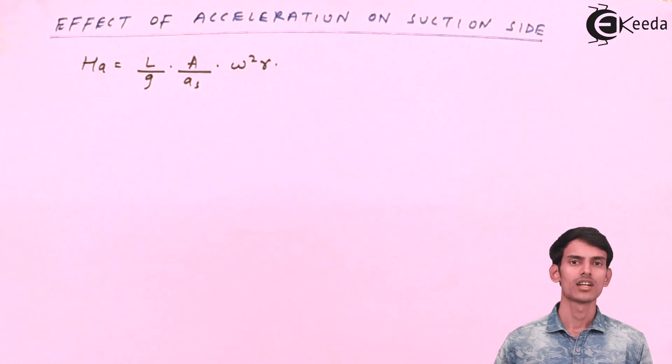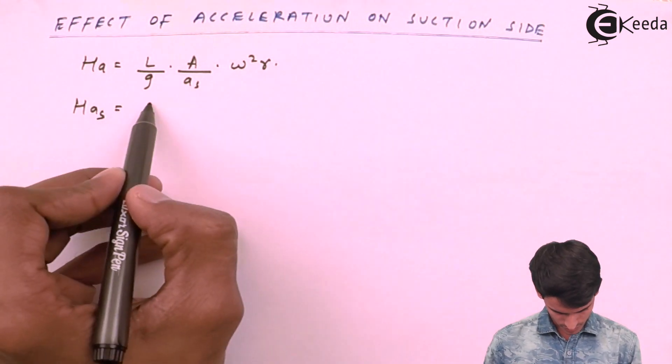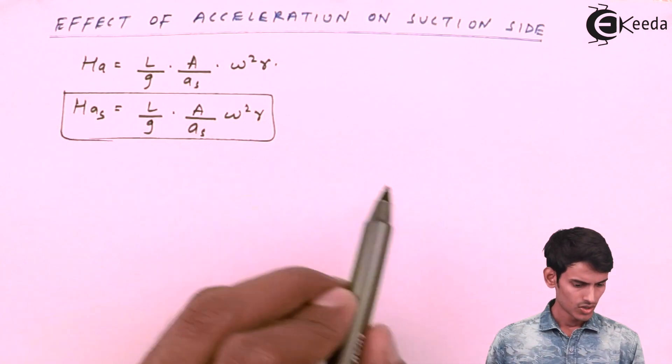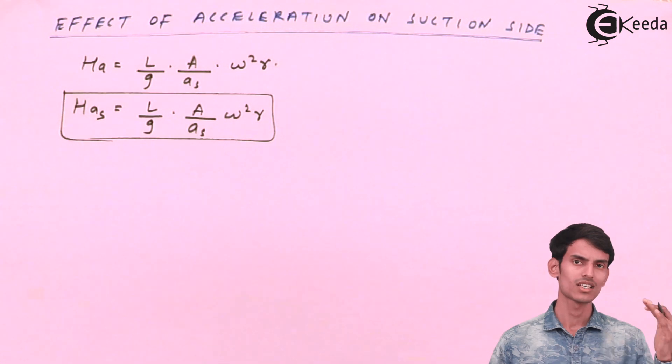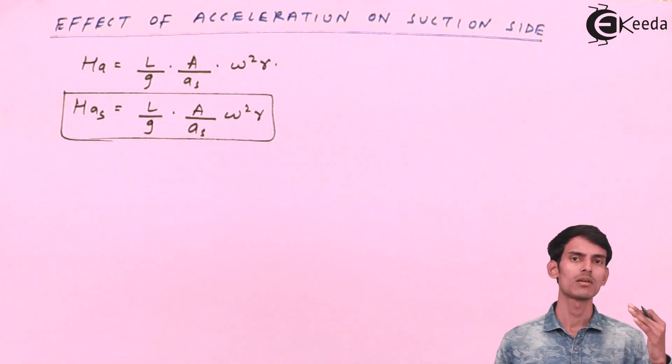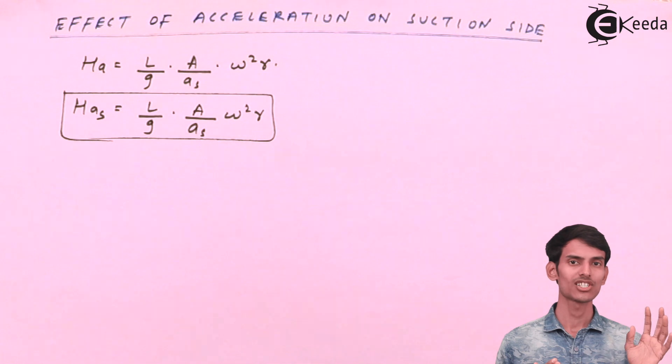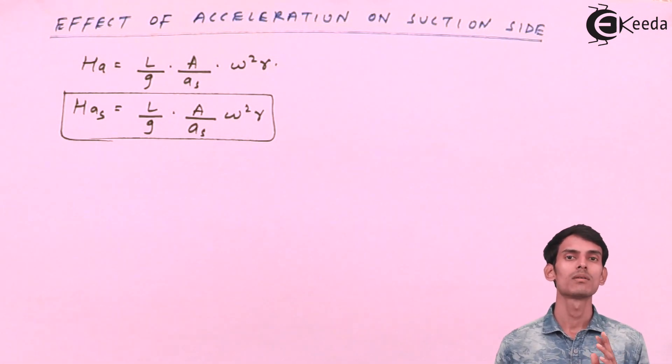So this is the acceleration head. Acceleration head at the suction side. Now since the water is accelerating in the suction pipe, there is HS that is the height through which it has to be pumped. And since it is accelerating, so the total vacuum that it has to create is nothing but HS plus HAS. So that is the total vacuum that the pump has to create so that the water comes inside the pump.